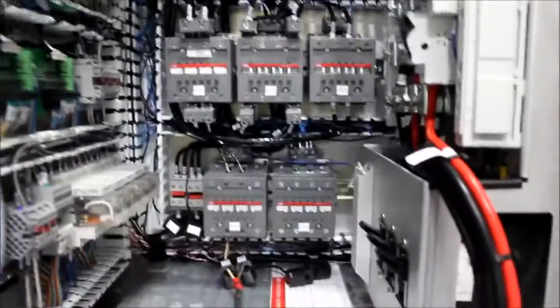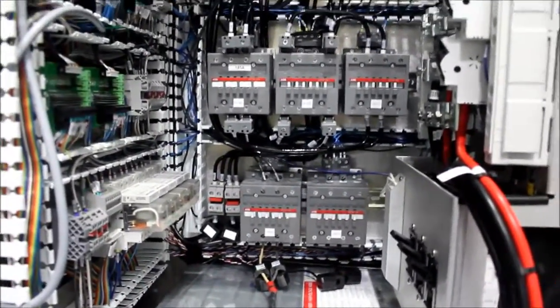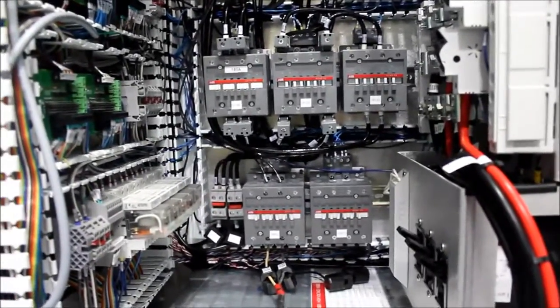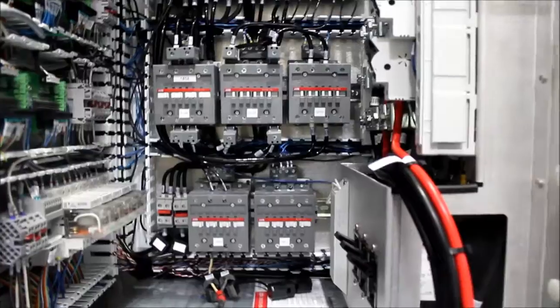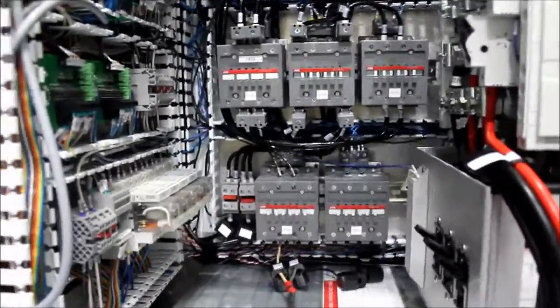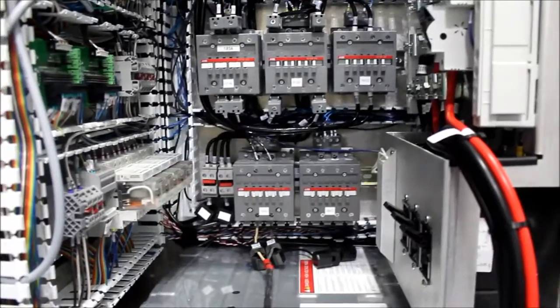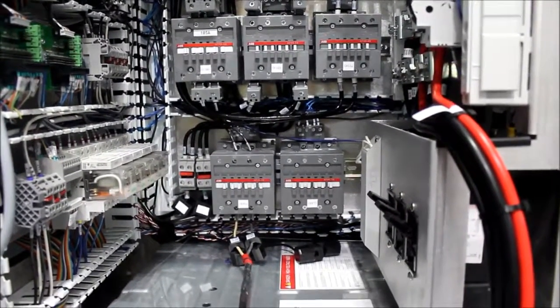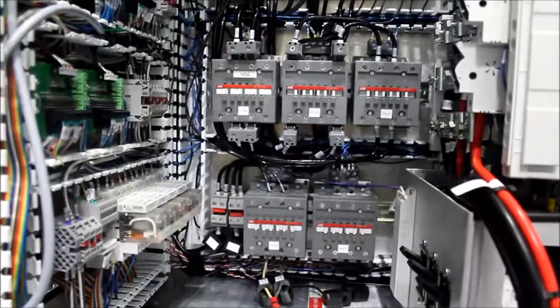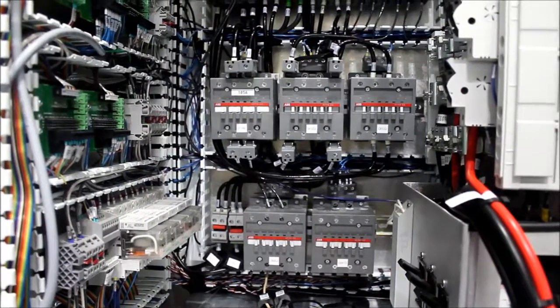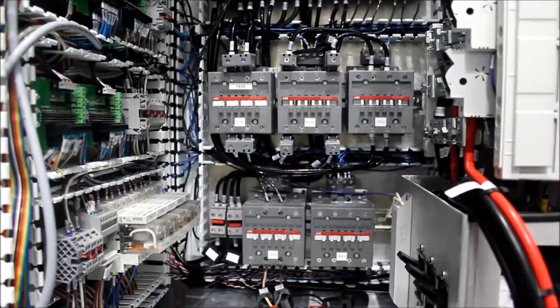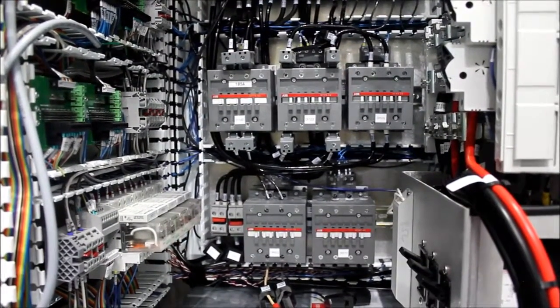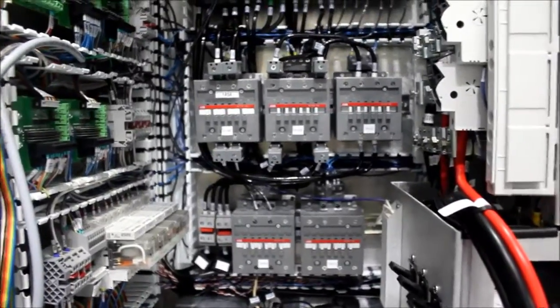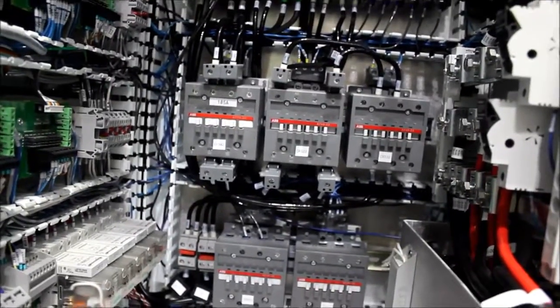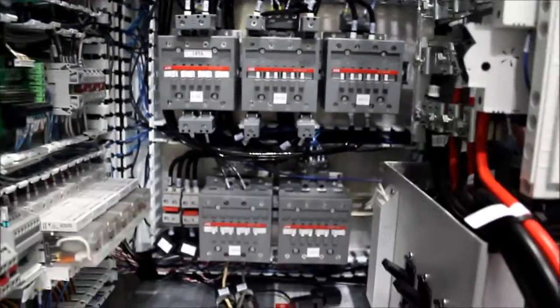Page 200 of the energy switch schematic shows the main mode switching and energy routing contactors. Many of those are shown directly in front of you. They are internal to the unit. For instance, CR522 is one of the relays, or contactors, used for the inverter, photovoltaic legacy grid-tied inverter output routing, and that is shown directly in front of you. Many of the other ones on that sheet 200 are here as well.